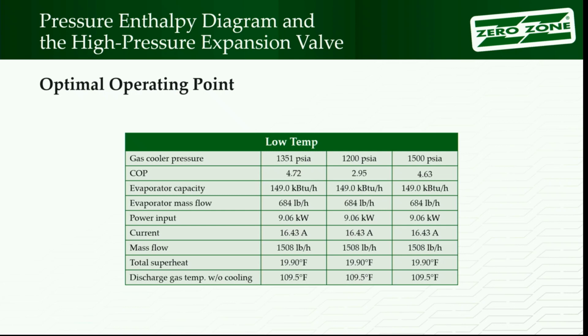And some of these numbers, when you look at them, they don't have a big number change by itself. You think, well, okay, it went from around 3 to 4 3/4. What's 1 1/4? When you look at the percent change, it's over a 33% change. So again, when you deal with small numbers, it's the percent difference that changed, not the absolute value. Change by a degree. Well, how much cooling you're doing? Well, we're only trying to cool at 5 degrees and I'm off by a degree. That's a 20% difference. So you got to be aware of that when you look at these. Small numbers can be significant on the electric bill.